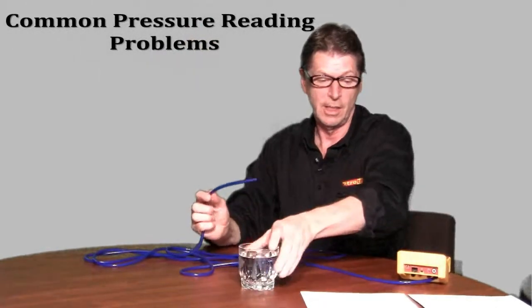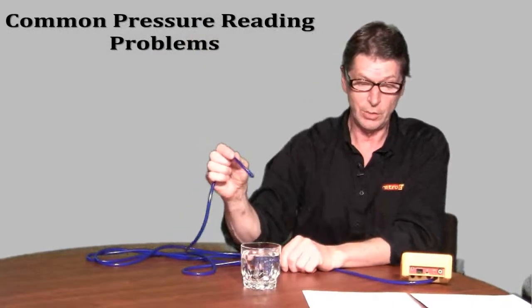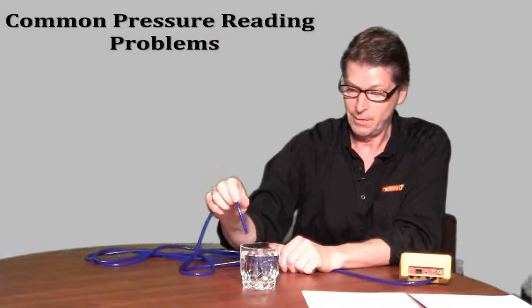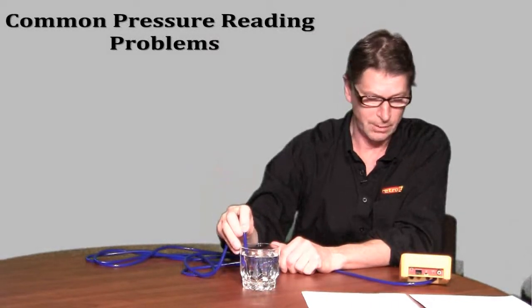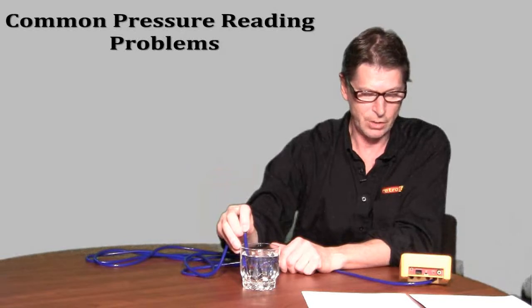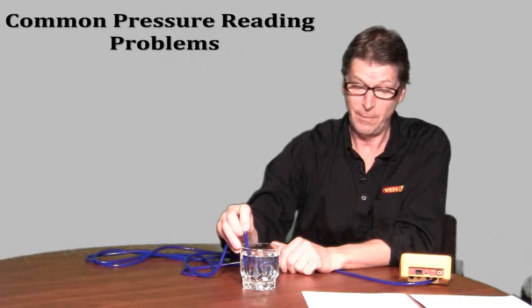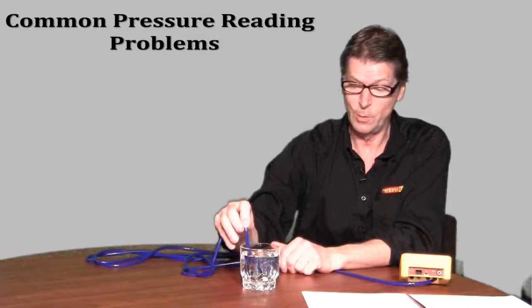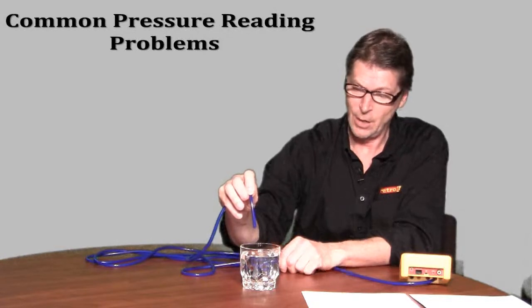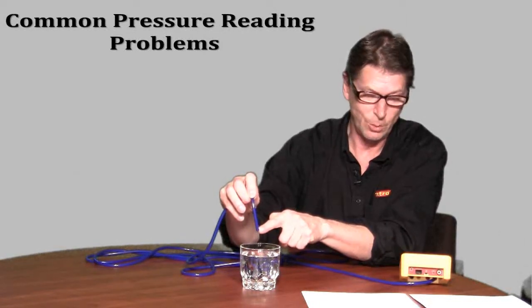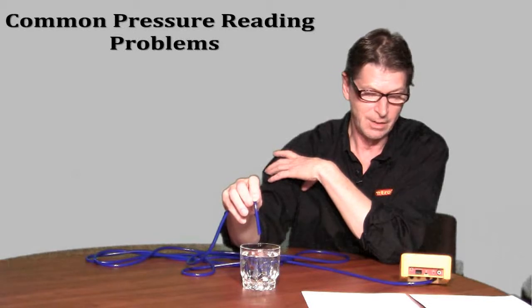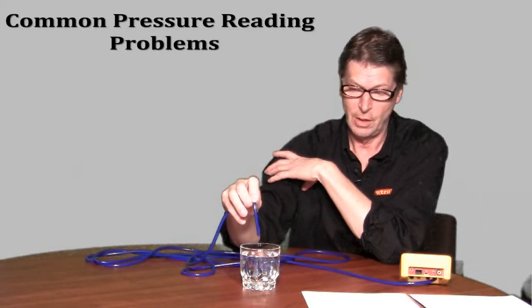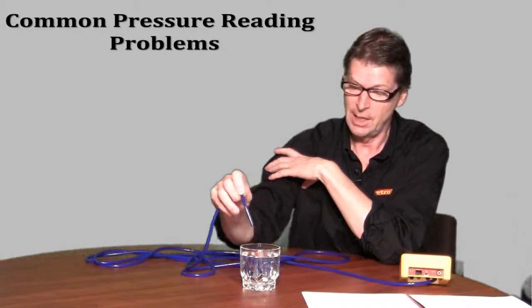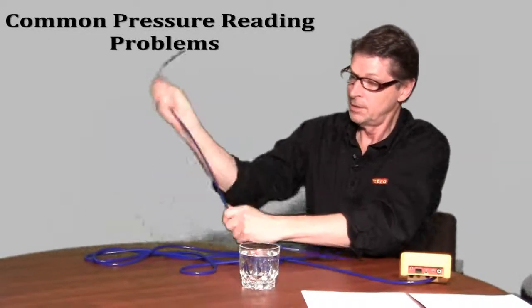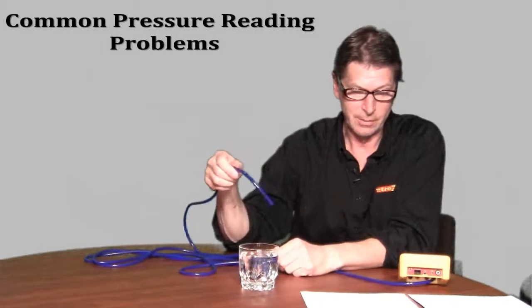Step 3 is to submerge the tube 1 inch into a glass of water to simulate the effect of your tubes falling into a puddle, and observe the pressure being displayed on the gauge. Step 4 is to remove the tube from the water and allow a drop of water to hang from the end of the tube, and notice the effect of the pressure of that water on the gauge. Now whip the end of the tube a little bit to get rid of that water.